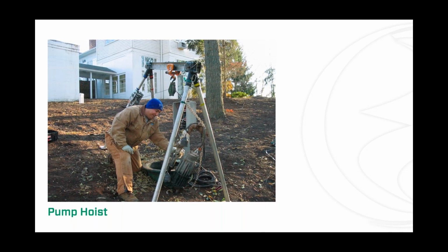Talking about servicing pumps, a pump hoist is going to save your back and keep you from hurting yourself. As you get into bigger pumps, a pump hoist of some sort becomes necessary. For you, that might be a big crane truck, but there are pits where you can't use a crane truck - these pits sometimes get installed in basements or other strange locations. So having some type of mechanical system to safely hoist pumps in and out of these pits is recommended. No matter what you choose, make sure it's safe - it's not worth hurting yourself over.